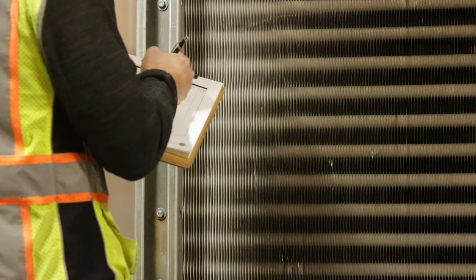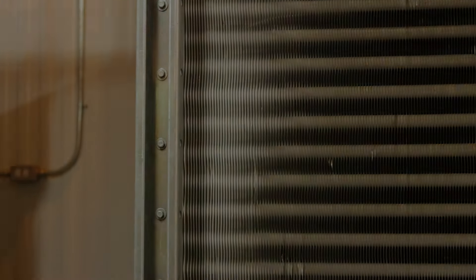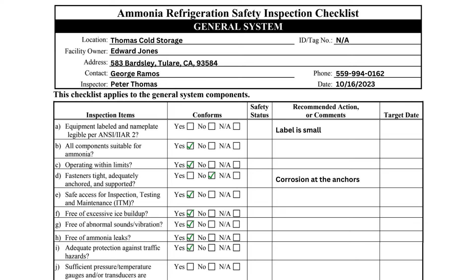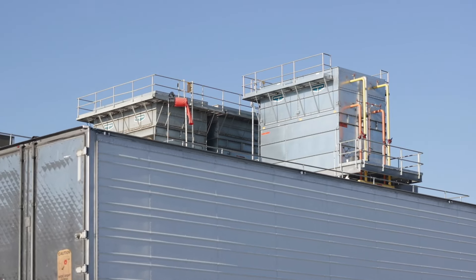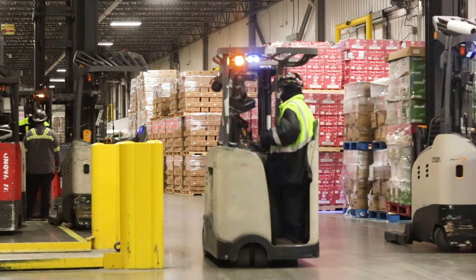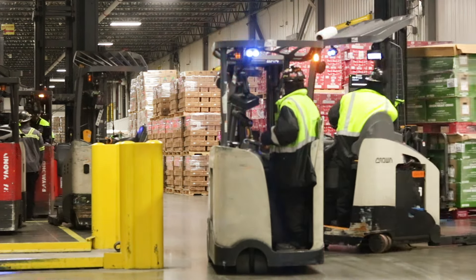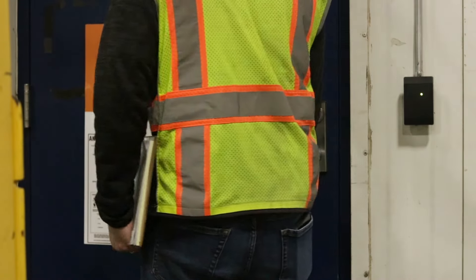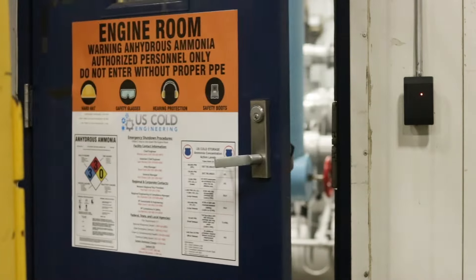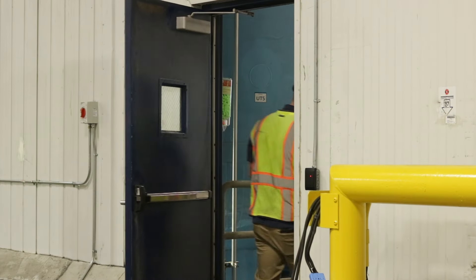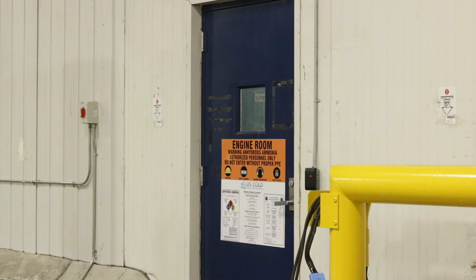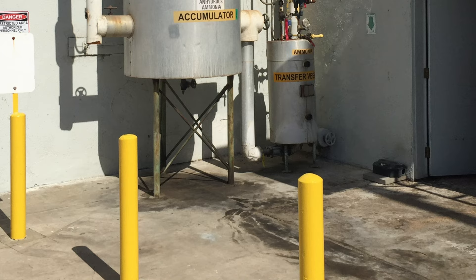Excessive ice on the evaporator fins will reduce efficiency and indicates that the units are not being properly defrosted. Item I asks if there is adequate protection against traffic hazards. Refrigeration equipment can be located throughout the facility and it's imperative components are adequately protected from potential impacts from forklifts, aerial lifts, service trucks, or semi-trailers. It is not uncommon for ammonia piping bridges to extend throughout the facility and be located in heavily trafficked areas. Machinery rooms protect much of the high-side equipment from contact, but where equipment is stored outdoors, barrier posts can also protect the equipment from impact.